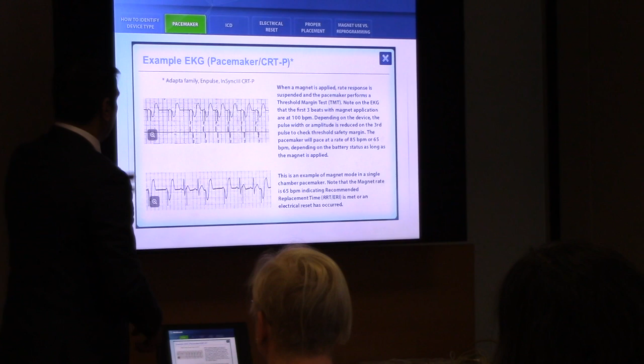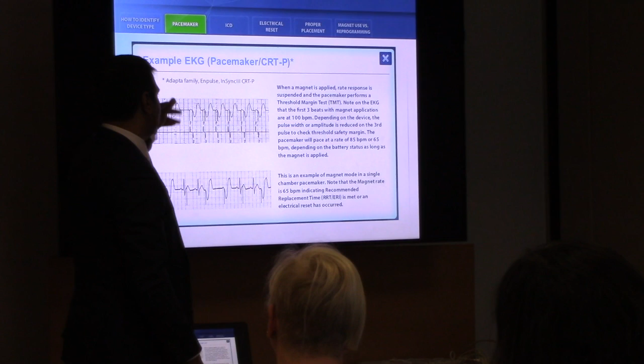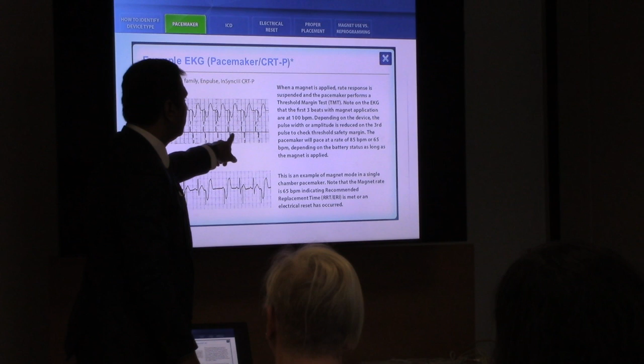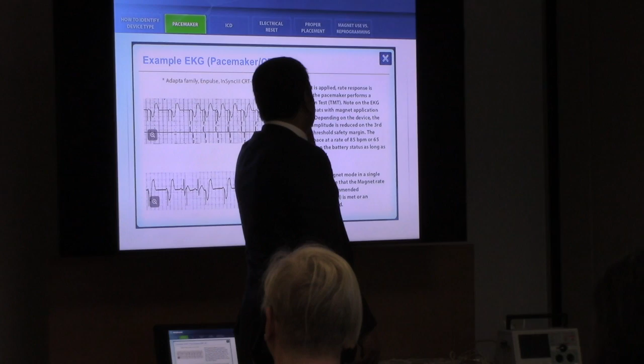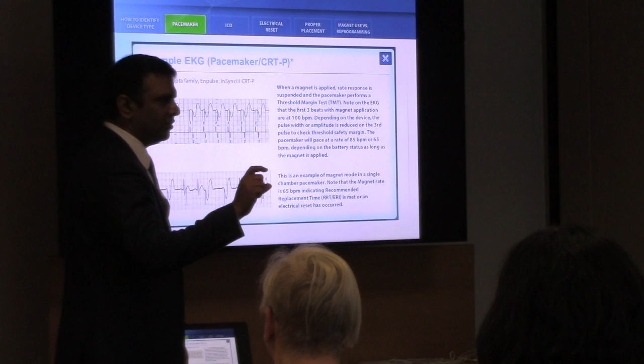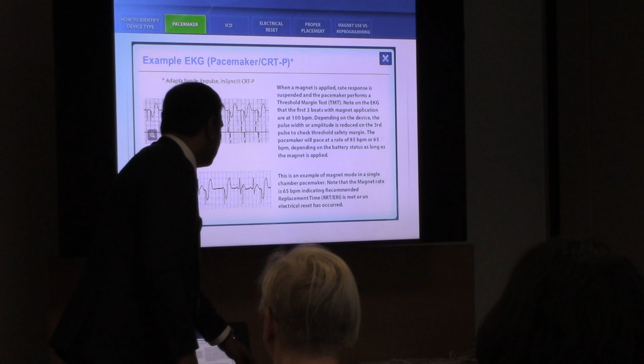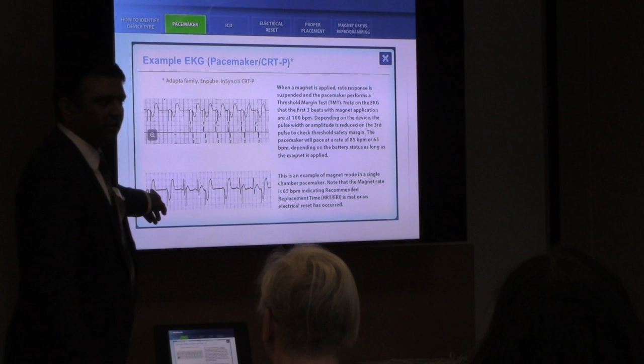So this is an example of an EKG, a CRTP actually, that had a magnet placed over it, and then it went DOO. So the first 3 beats in a CRTP would be 100 beats, and then the rest would go to 85. So there's a slight difference if they had a CRTP. And this is close to end of life, they're just going at 65. RRT, I told you, is recommended replacement time.